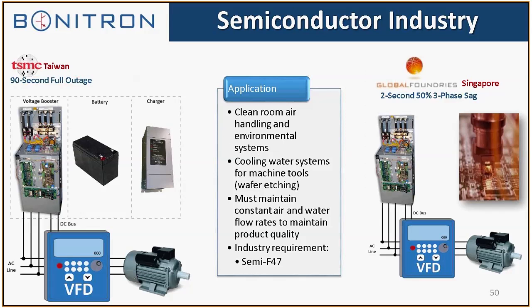This shows you the correlation between regional type specifications, 90-second full outage overseas in the Asia market, to a 2-second 50% sag in Singapore for semiconductor. The interesting thing about this is the same company that we did the sag ride-through in Singapore required full outage in the United States. So specs can vary with companies, but mainly they're geared around the utility power event that's going on in the region, how stiff the grid is.